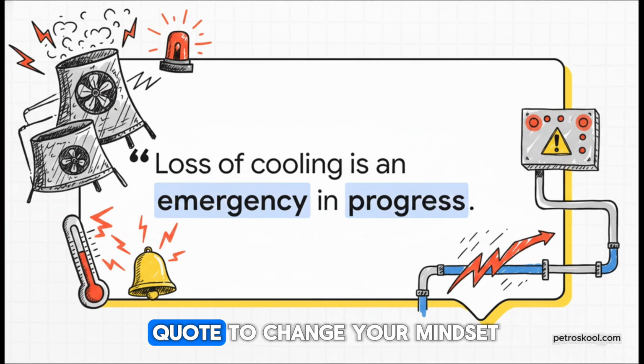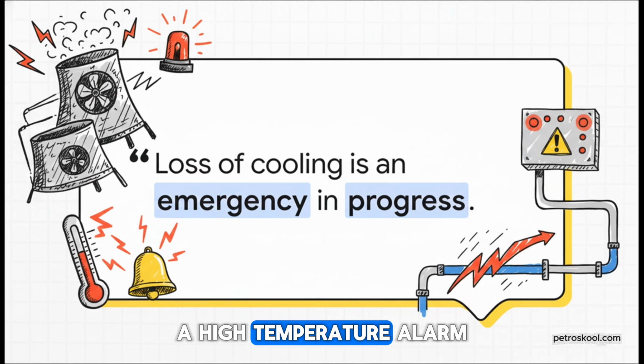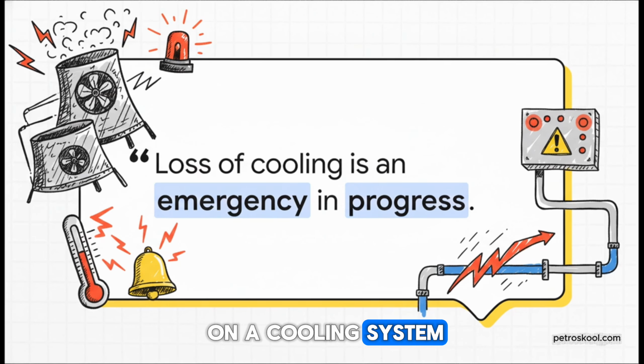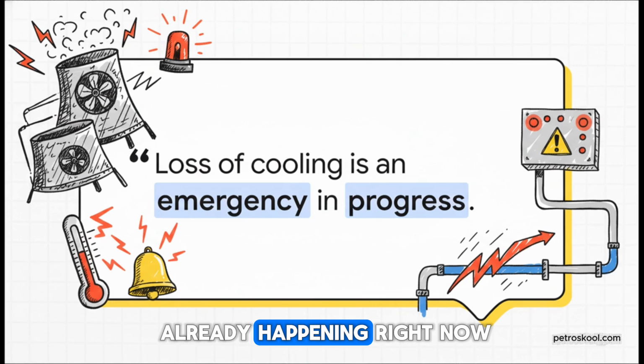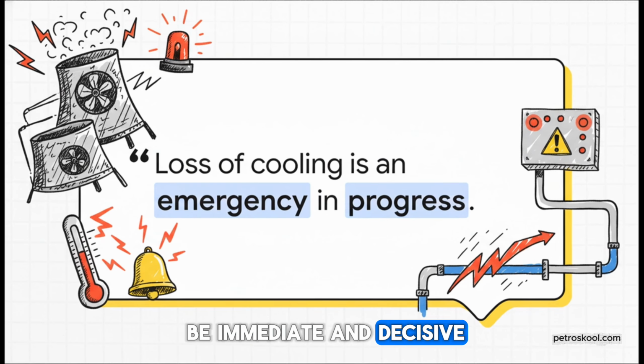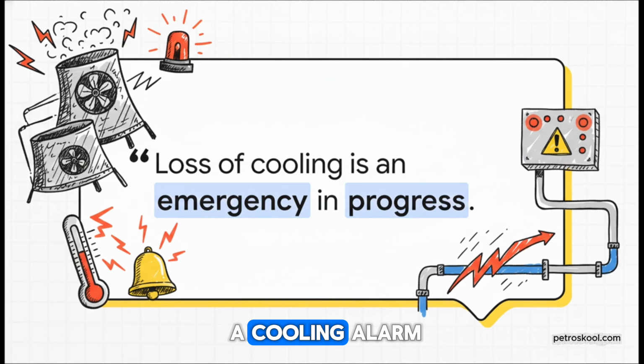I really want this quote to change your mindset: a high-temperature alarm on a cooling system isn't a warning that a problem might happen in the future. It is a notification that an emergency is already happening, right now. Your response has to be immediate and decisive. Never, ever, ever ignore a cooling alarm.